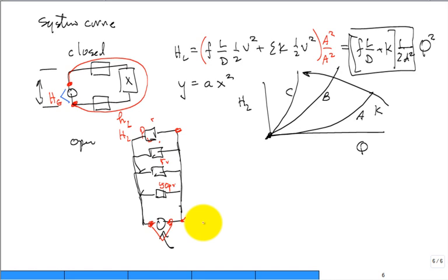It's bad logic for a closed system because, yeah, you're pushing it up on this side, but what's coming down there? And so for a closed system, in the equation for the head loss, there is no delta Z. There is no delta Z. Guess what about for the open system? I got to go to another page. But I see that, oh no, we need a bigger motor and a bigger pump because it's got to go up that high in the building. Okay, let's go down to the open system.